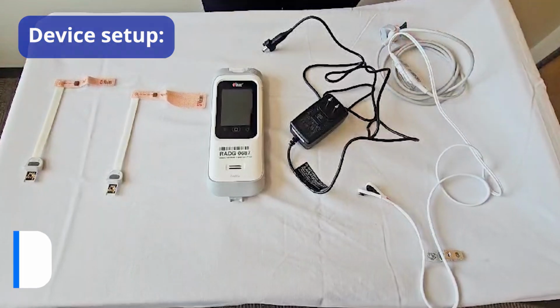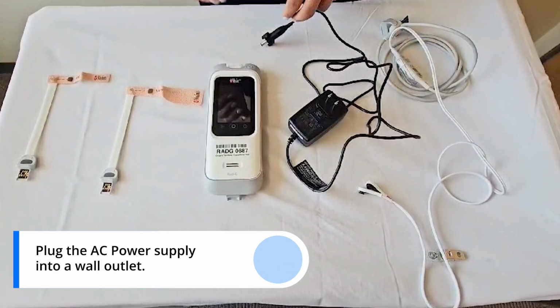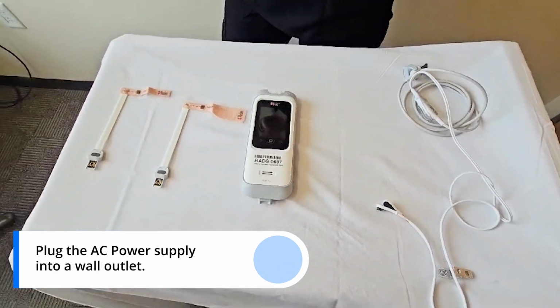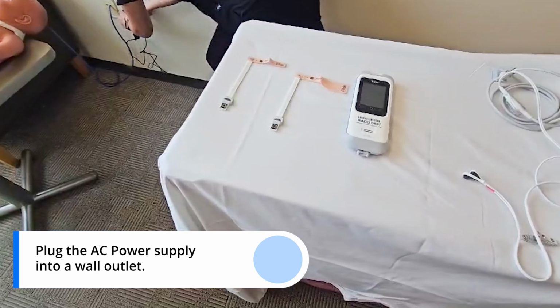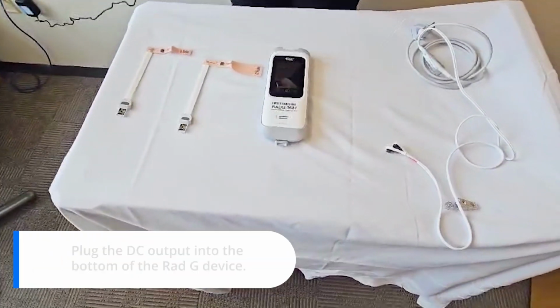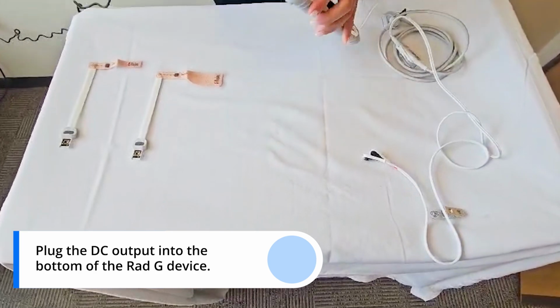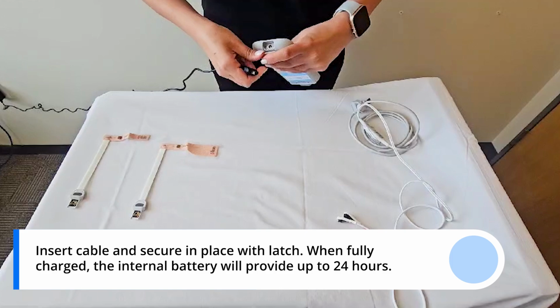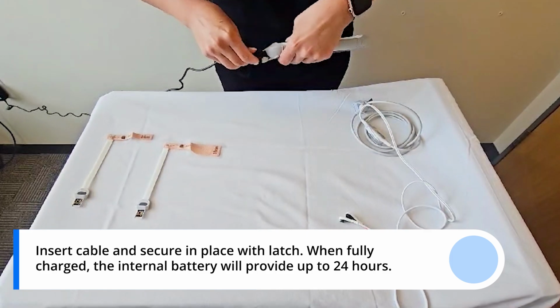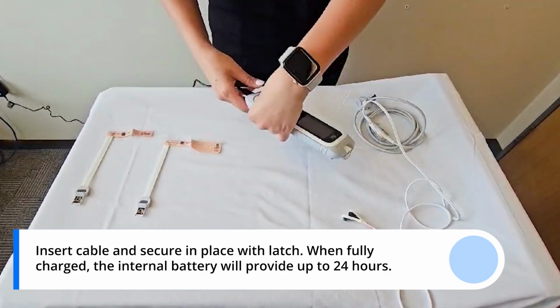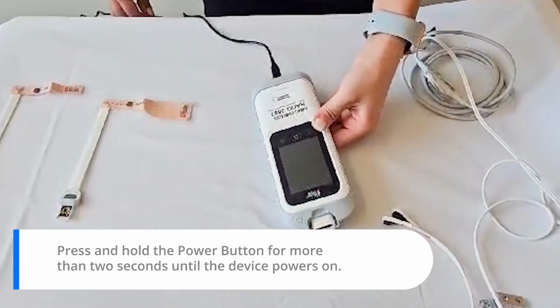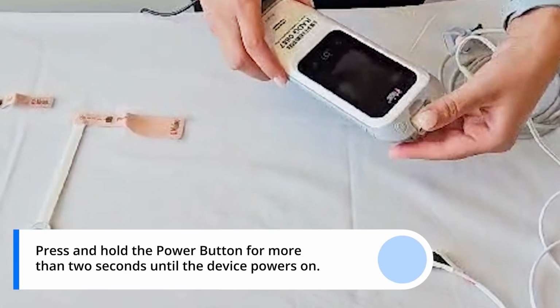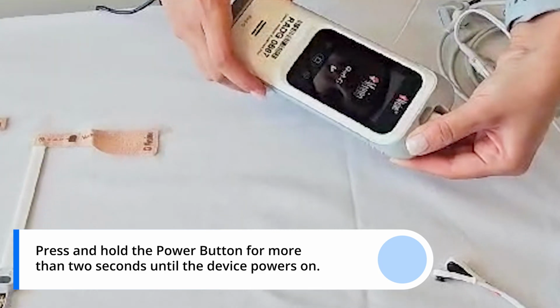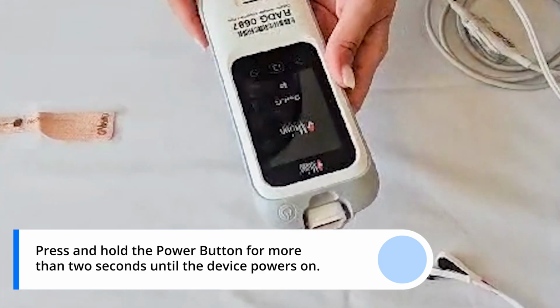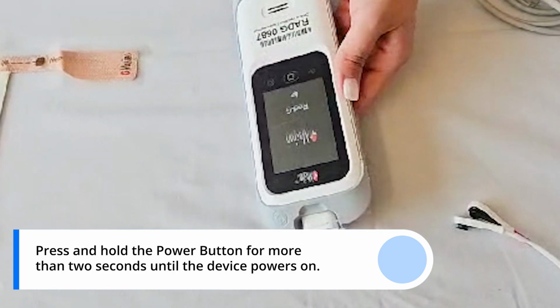To set up your device, plug the AC power supply into a wall outlet and the DC output into the bottom of the Rad G device. Insert the cable and secure in place with the latch. When fully charged, the internal battery will provide up to 24 hours. Press and hold the power button for more than 2 seconds until the device powers on. You will hear one audible tone sound when the device turns on.